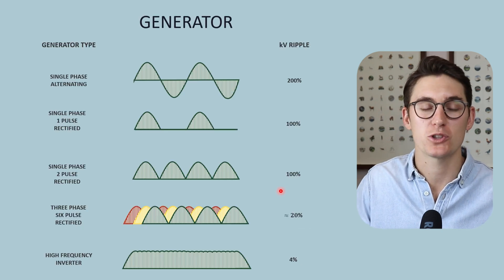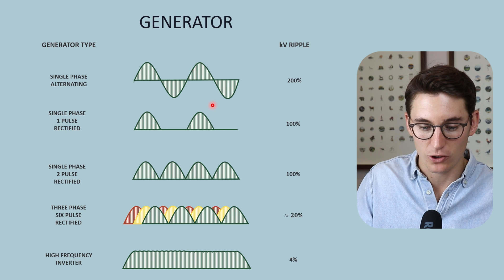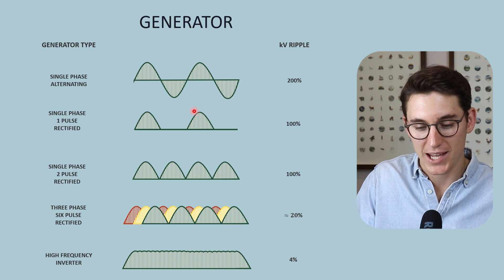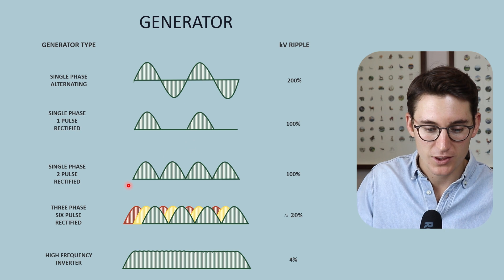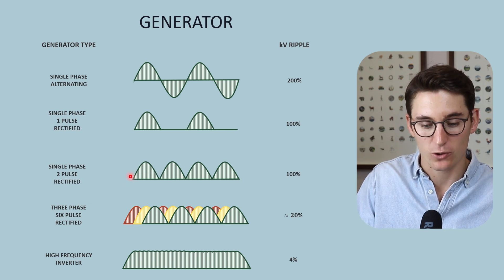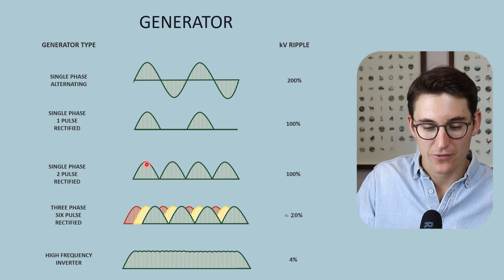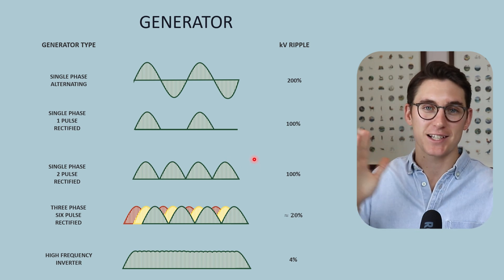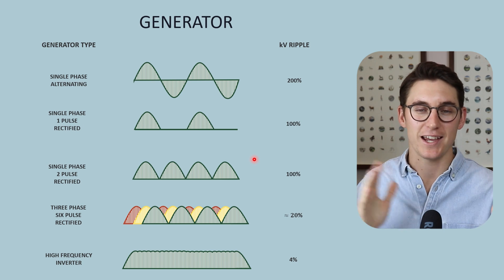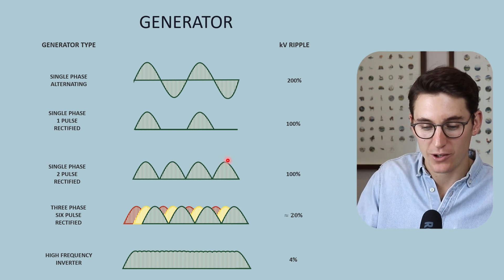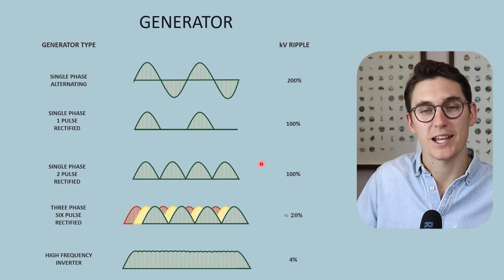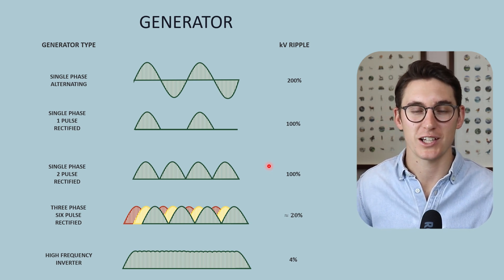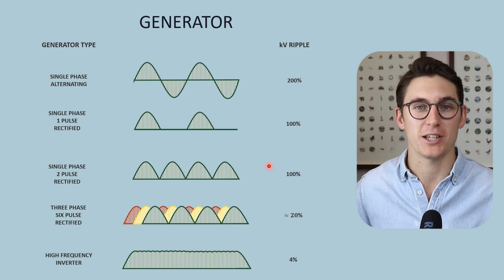When talking about waveform, our KV ripple is the difference between our KVP — our kilovolt peak — and our baseline. With a single phase two-pulse rectified or full wave rectified waveform, we get voltage fluctuations that range from zero to our KVP. The electrons being accelerated towards our anode fluctuate in their energy levels — they will have periods where they reach our KVP, but for most of the time those electrons will have lower energies, resulting in a lower energy x-ray spectrum and lower beam quality.